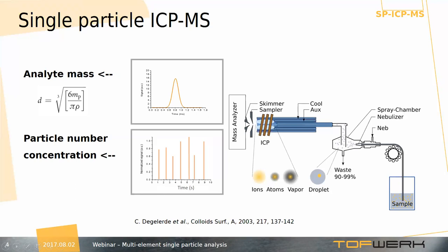The suspension has to be diluted in such a way that only a small fraction of these droplets contain particles and only one particle enters the ionization source at a time. When a droplet containing particles enters the ICP, it undergoes vaporization and atomization, forming an atomic cloud of ions which are sampled from the atmospheric pressure ICP into the mass spectrometer. The ions are separated according to their mass-to-charge ratio inside the mass analyzer and detected in the form of extremely short transient signals, lasting usually a fraction of a millisecond.